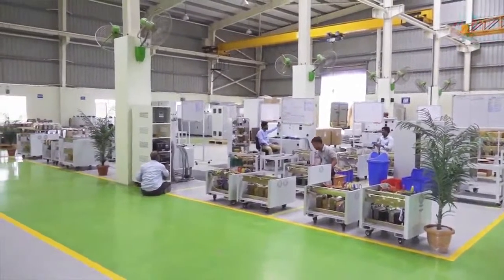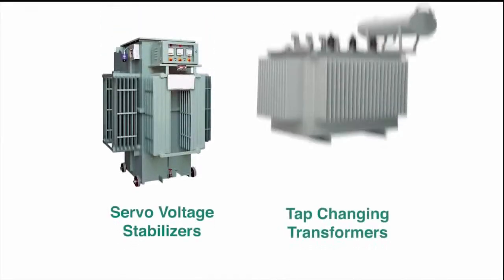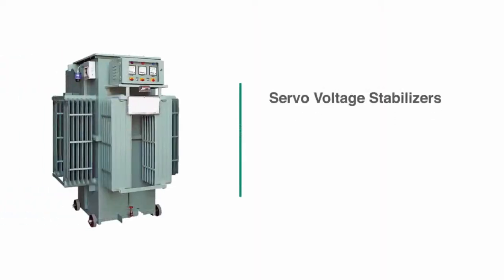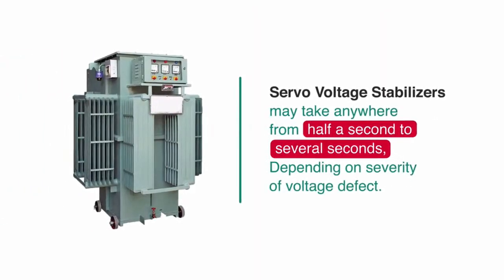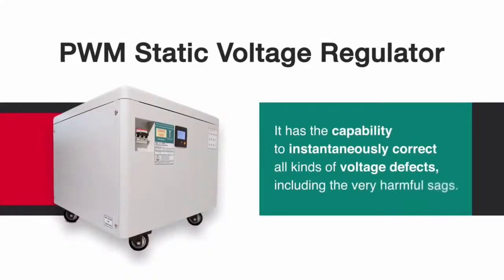This is easier said than done by conventional technologies like servo voltage stabilizers or tap-changing transformers, because these may take anywhere from half a second to several seconds depending on the severity of the voltage defect. The ideal solution is a static voltage regulator which has the capability to instantaneously correct all kinds of voltage defects, including the very harmful sags.